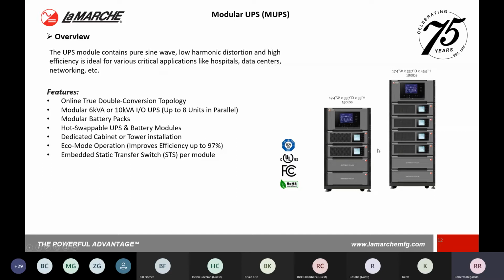They are hot swappable, so you can go ahead and remove these power modules and battery modules. So that does give you a better MTTR, or your mean time to repair, and even a lower MTBF in a lot of cases. You do have a couple mounting configurations. You do have the cabinet style, which are these designated cabinets because they do have a built-in rear bus that you would have to connect with. So it is something that you do have to designate as far as using these cabinets. And you do also have the single modular tower style configuration that we saw with the compact UPS as well.